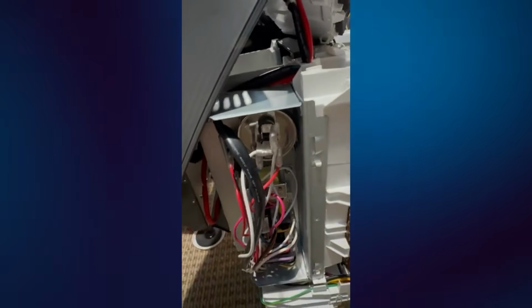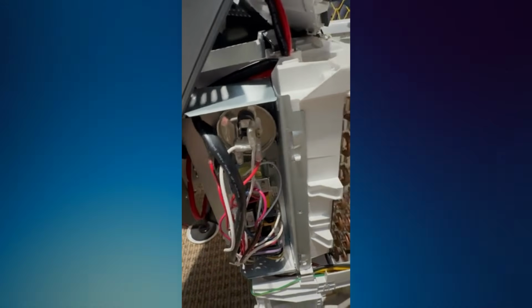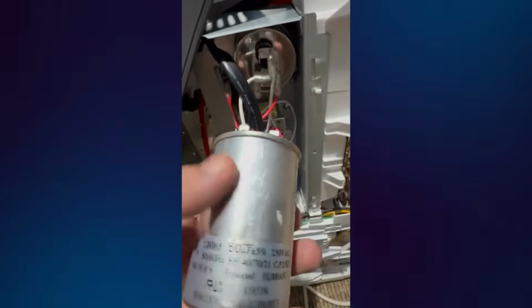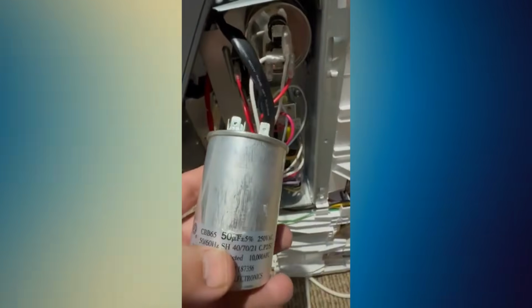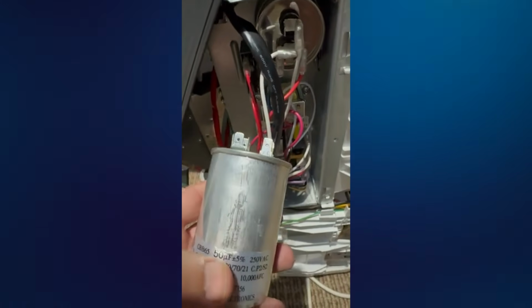One reported repair involved a dehumidifier that repeatedly displayed E9 even after the sensor had been cleaned and replaced. In that case, replacing the compressor run capacitor allowed the compressor to start and the unit began operating normally again. This is a possible cause, but it is not a universal E9 repair. Do not order a capacitor until the original component has been properly tested.